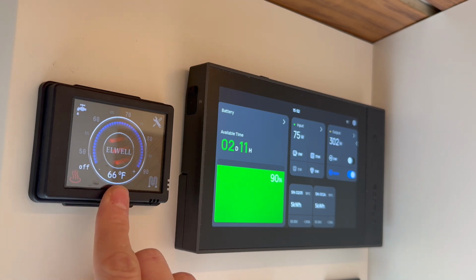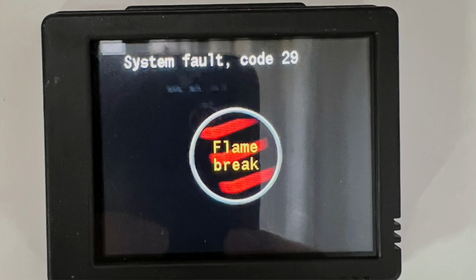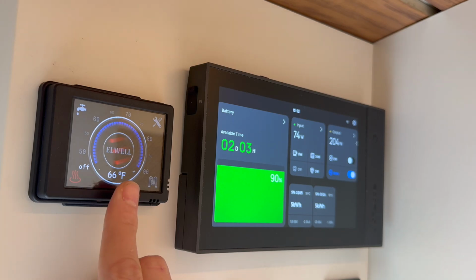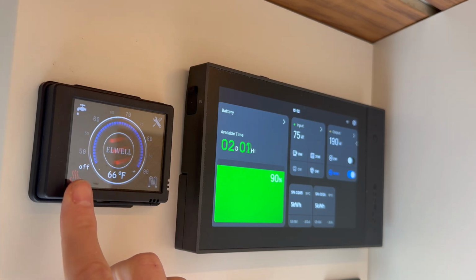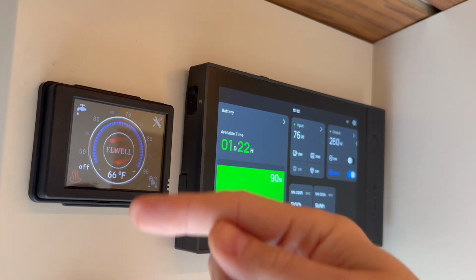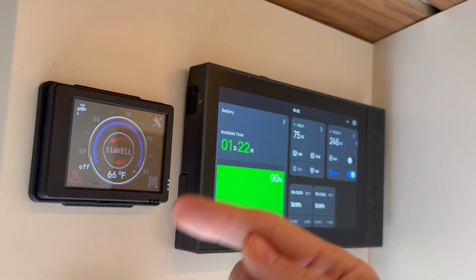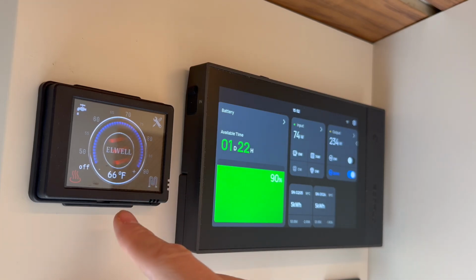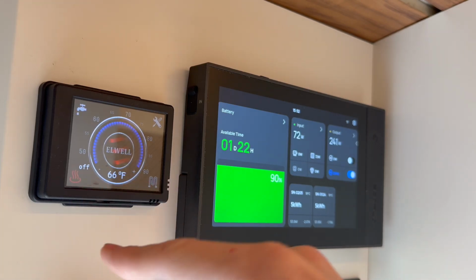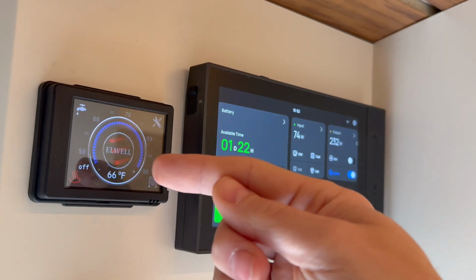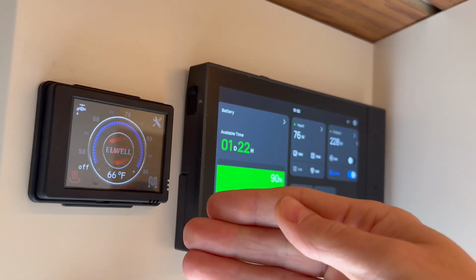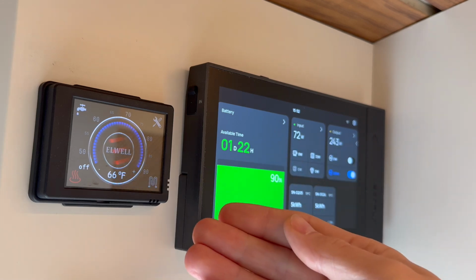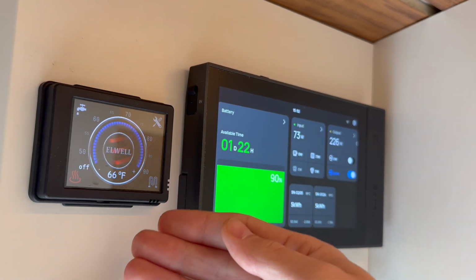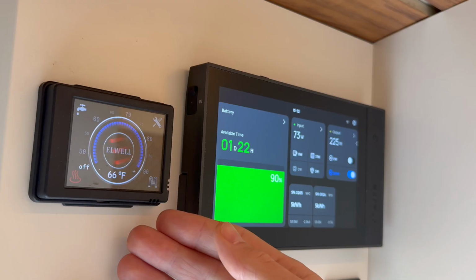You will get an error code called flame break. Don't worry about this, it just means that the system is unprimed. When you see that code, just click again on that button to restart it. The fuel will go in the lines again and will start to ignite the burner. If you get that error code again, do the same process. It can take 2, 3, or 4 times for the fuel to get to the burner and for the burner to actually start. Do not think that there's a problem with the burner, it is just a fuel issue.